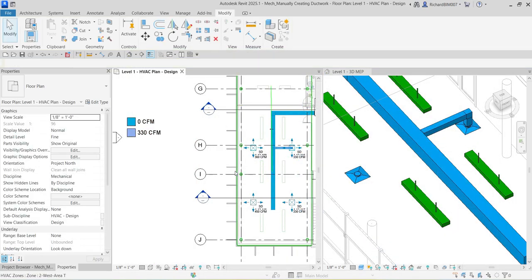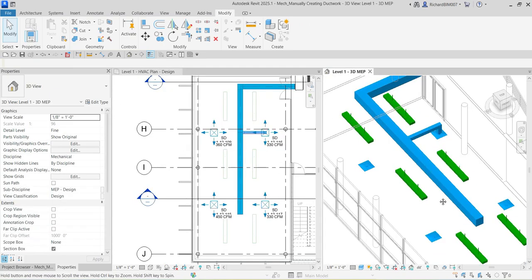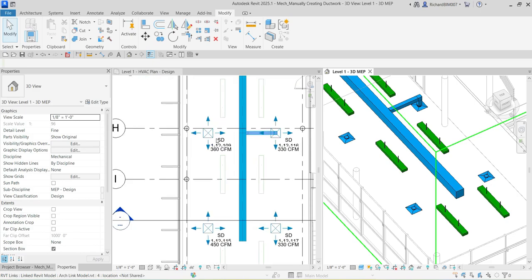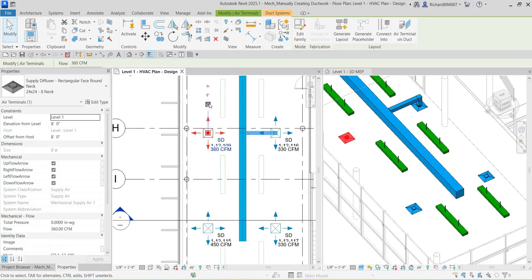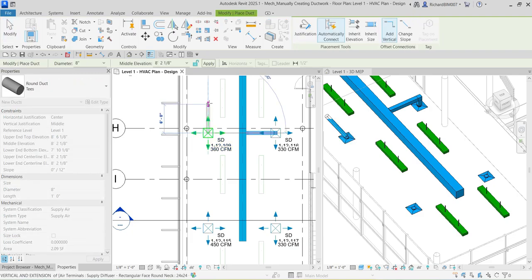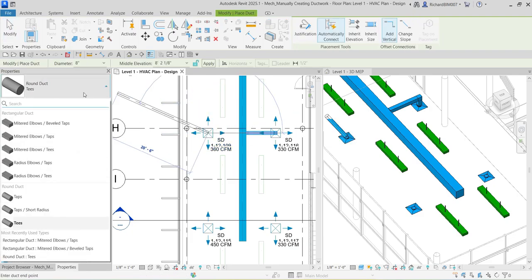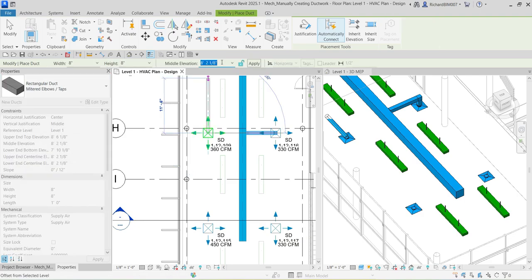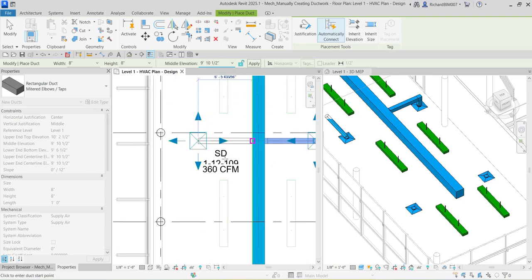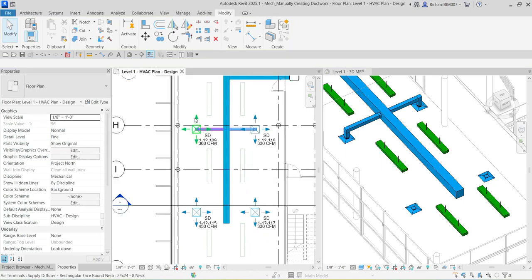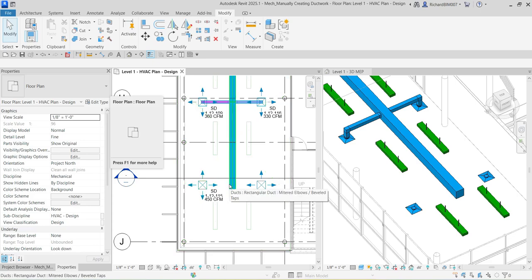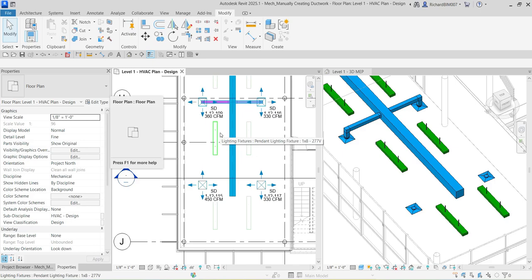We'll apply the same procedure to the other air terminals — click the terminal, click the connector icon, change the type to 'Mitered Elbows / Taps,' set the elevation to nine feet ten and a half, and place the duct. There is also another way to connect an air terminal to a duct using the 'Connect Into' tool. By the way, this procedure can also be applied to piping.